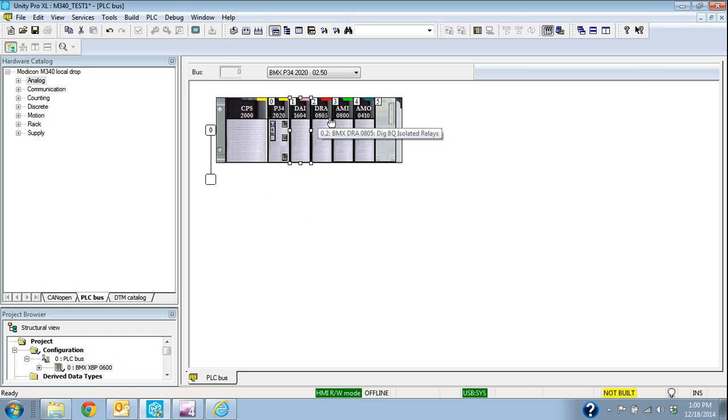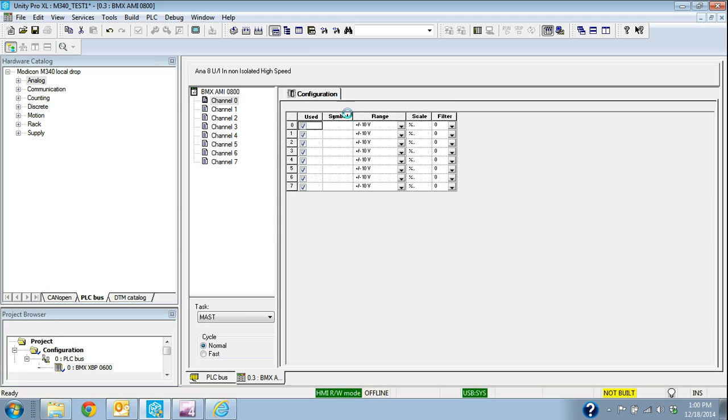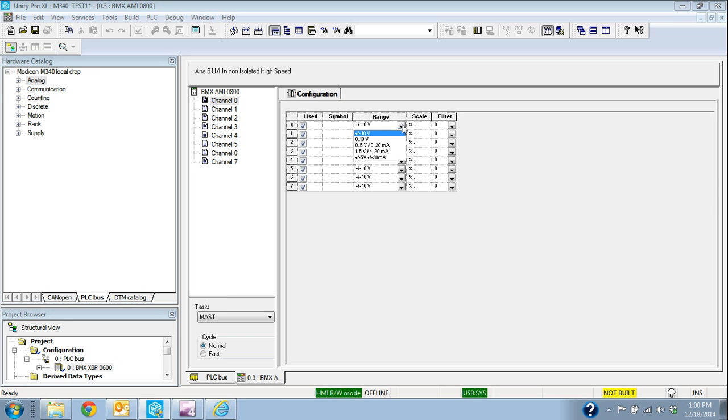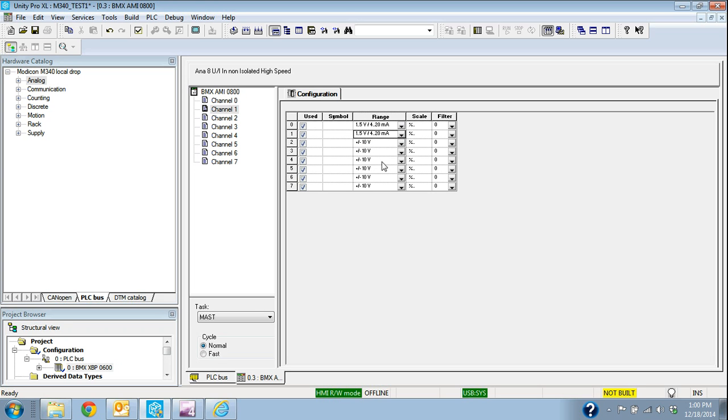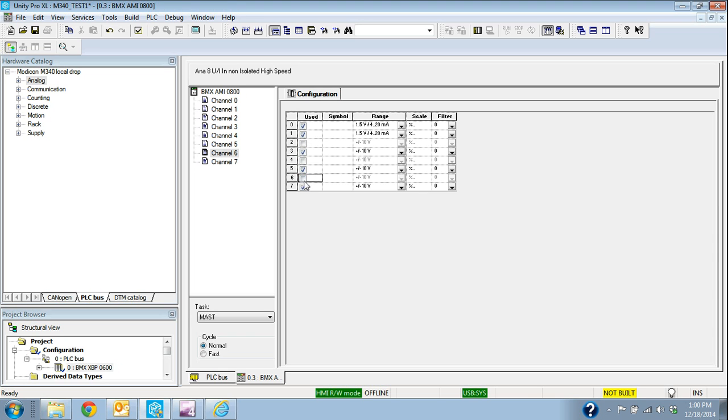If I go to the analog input card, I have an extra configuration on that card because it's analog, and one of the things that I would have to configure is maybe these channels. If these channels were 4 to 20, I would make that selection here, depending on what they were. Whether I was going to use them or not use them, if I was just going to use the first two and not use these ones, I could go and check those to say that I'm not going to use those channels.